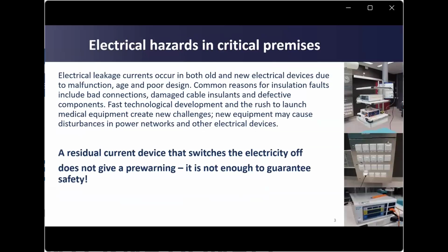Electrical leakage currents occur in both old and new electrical devices due to malfunction, age, and poor design. Common reasons for insulation faults include loose connections, damaged cable insulation, and defective components. Fast technological development and the rush to launch medical equipment create new challenges. New equipment may cause disturbances in the power network and other electrical devices. Please note that a residual current device that switches the electricity off does not give a pre-warning. It is not enough to guarantee safety.